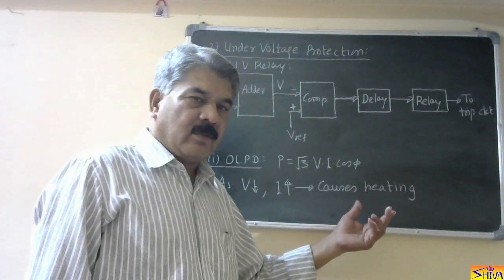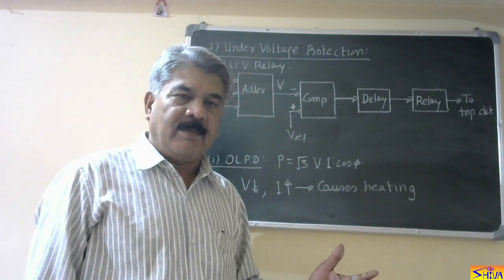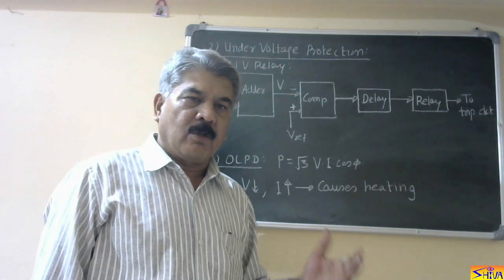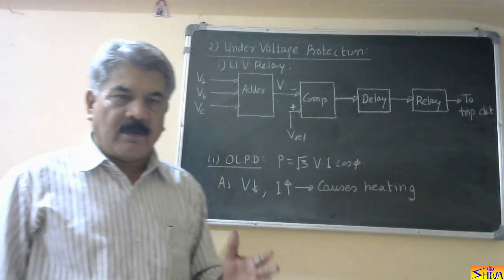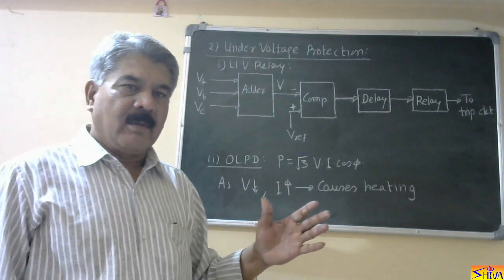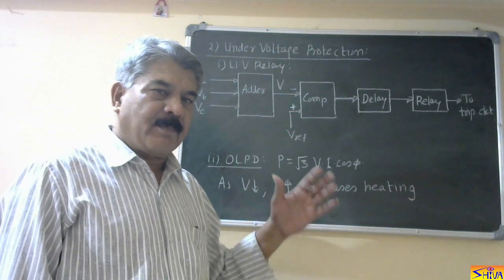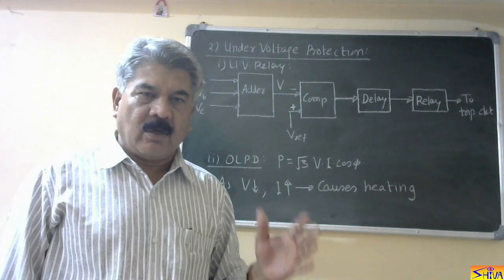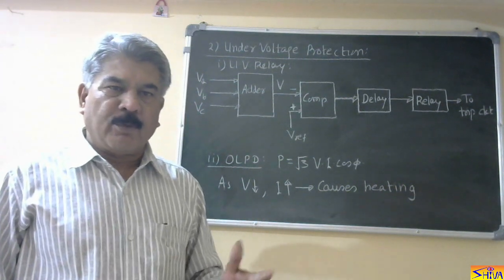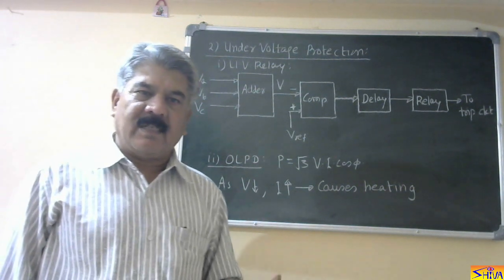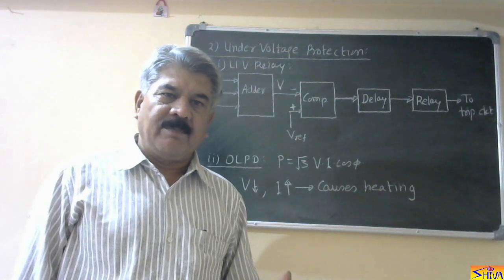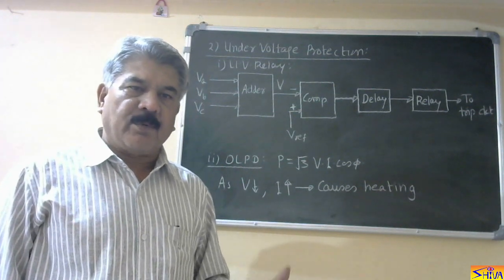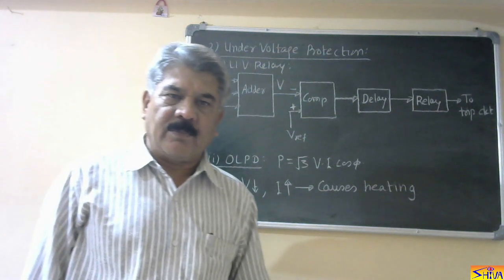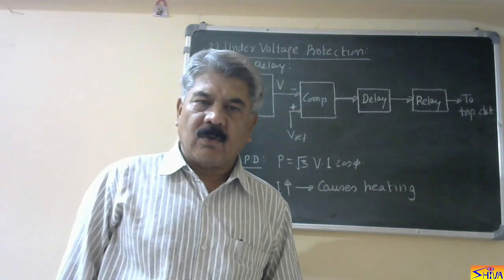This causes heating, so this can also be detected by the temperature sensing overload protective device. Therefore, for small induction motors and medium induction motors, separate under voltage protection is not necessary. An overload protective device of any type, that is current sensing or temperature sensing, is providing adequate protection for the under voltage condition also. Next is protection of the rotor.